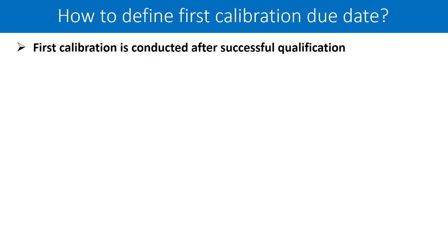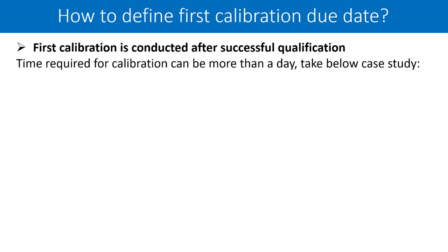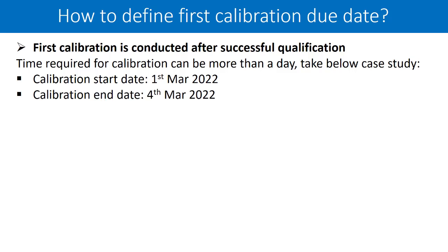The first calibration is conducted after successful qualification, as explained earlier. Now, most of the time, for complex calibration processes, you may require more than one day to complete the calibration activity. For example, an HPLC calibration cannot be completed within just one day. Let us take the following example as a case study. The calibration start date is 1st March 2022, and the calibration end date is 4th March 2022 — it took 4 days for completion.